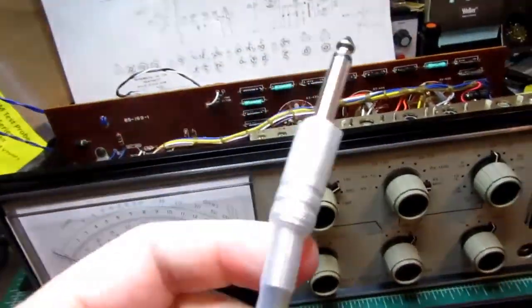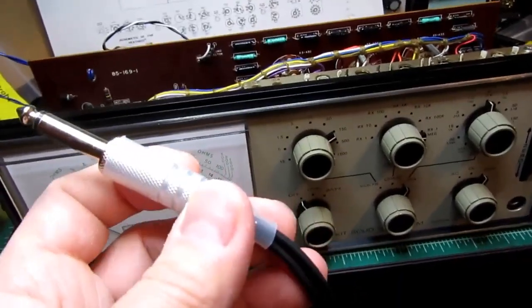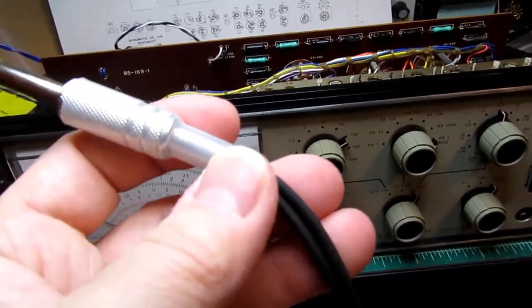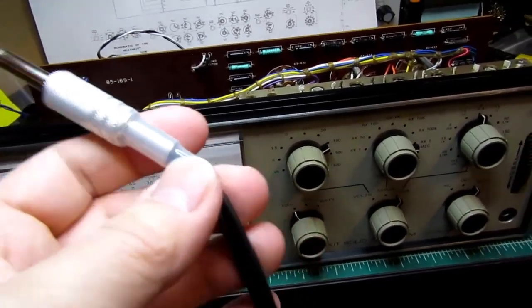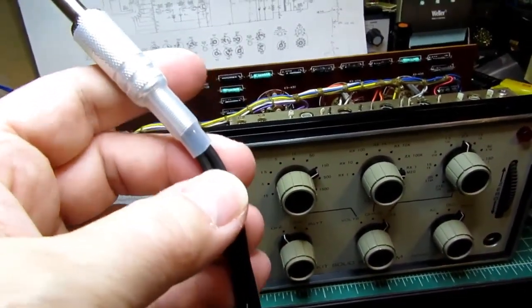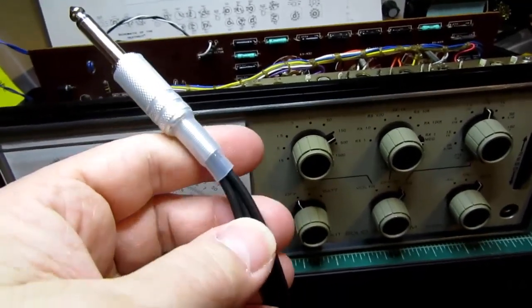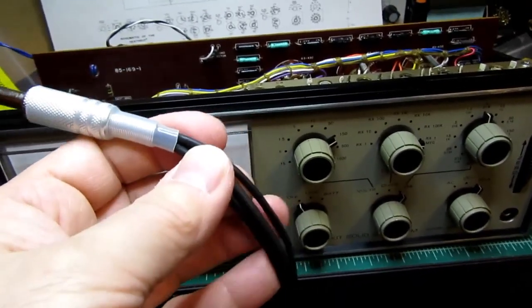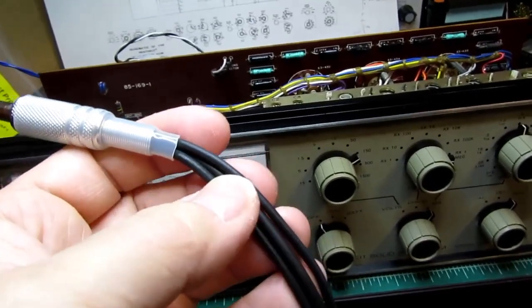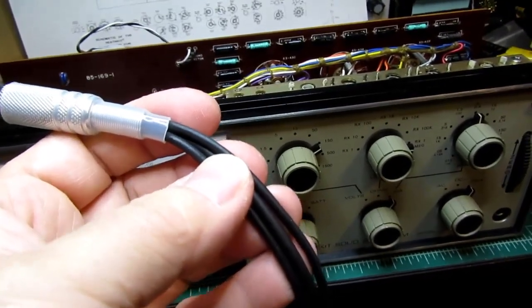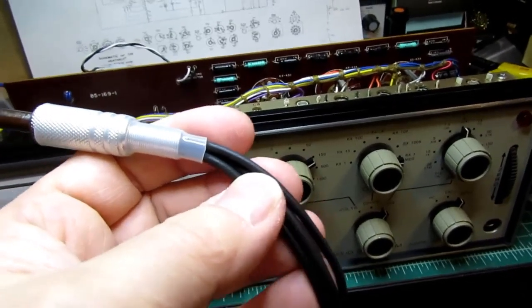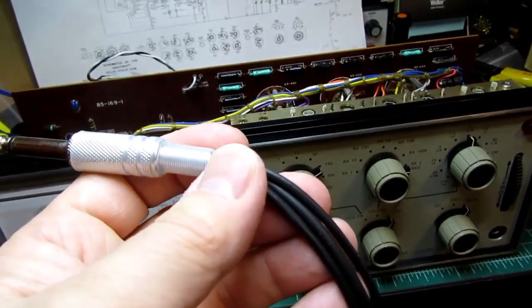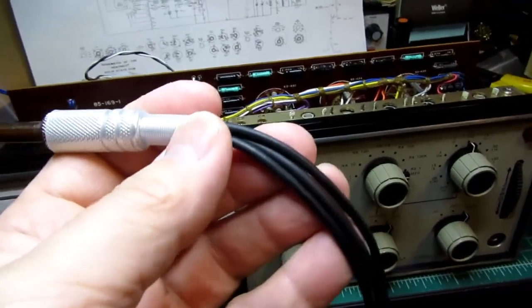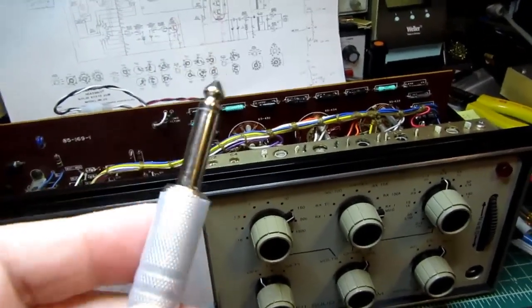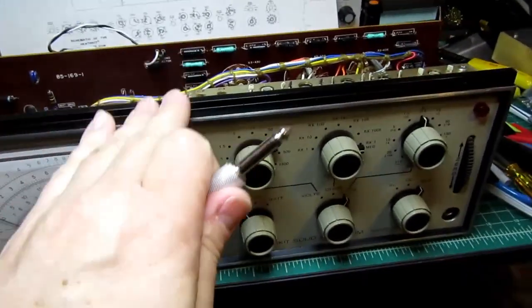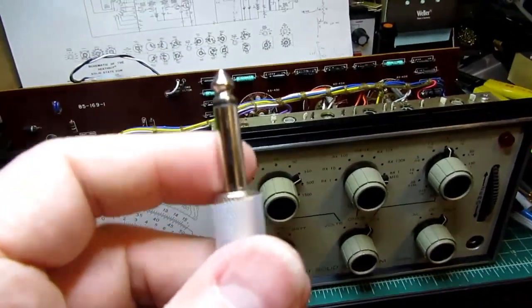So it won't work correctly if you use the wrong kind of test lead/probe setup. And it certainly won't work correctly if you try to use the probe with the 1 meg resistor in it for anything except DC volts. AC volts goes through a separate circuit, which doesn't want that 1 meg resistor there. Current certainly doesn't, and if you have a resistor of 1 megohms and you're trying to measure resistance, you've automatically added 1 megohm to whatever you're trying to measure, so that's no good. So again, only the DC volts measuring function of these meters needs to have that 1 meg resistor in there.